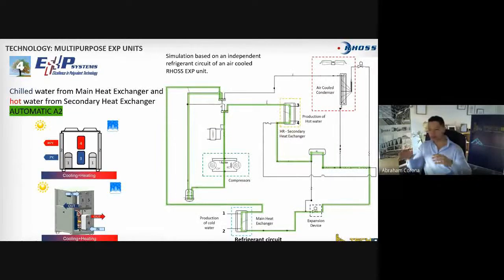Now we're getting to the middle season, maybe September, October, when there could be a demand for both. So now imagine that your chiller, looking at the cooling side, my water tank is still going above 7, so I still need cooling. But at the same time, we're starting to use heating. It could be a hospital, where you use heating even for dehumidification reasons, or probably you're using the heating because you are in the mid-season. For any reason, your design now requires heating the hot water tank and still having cooling water.